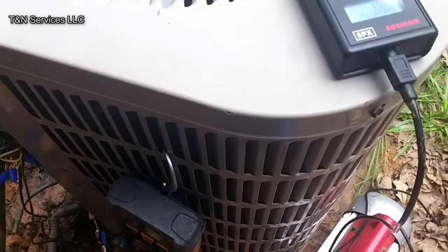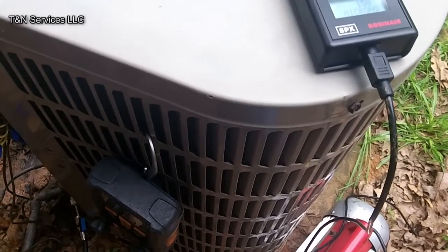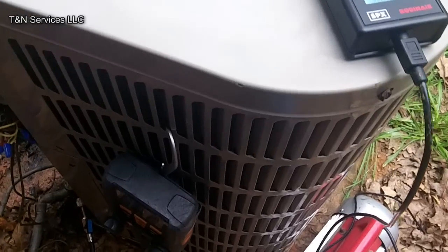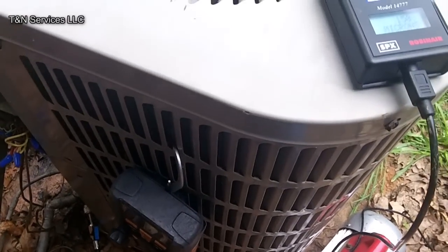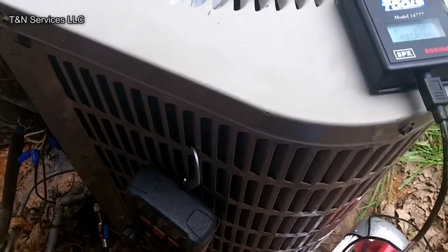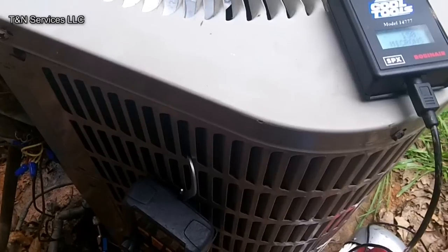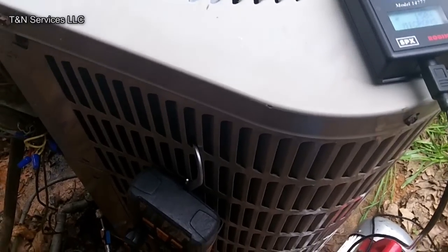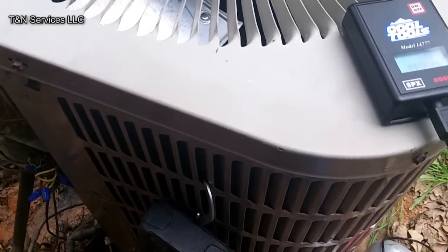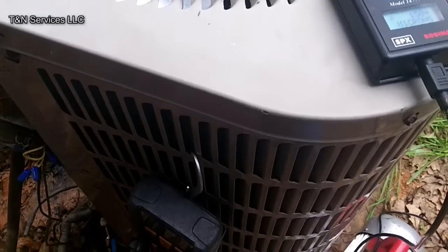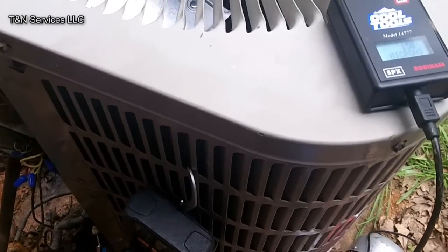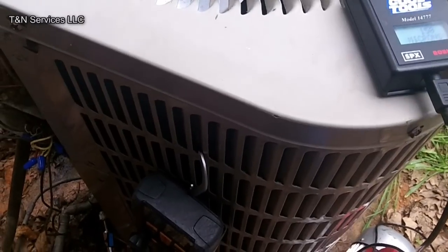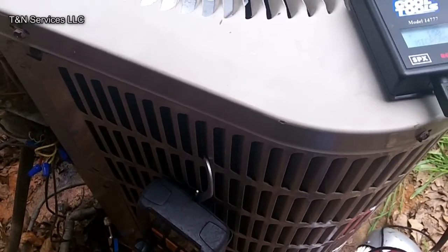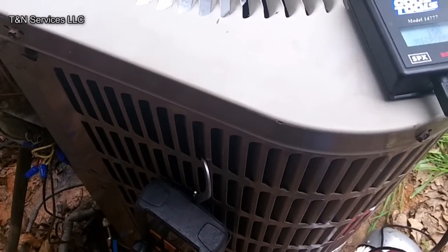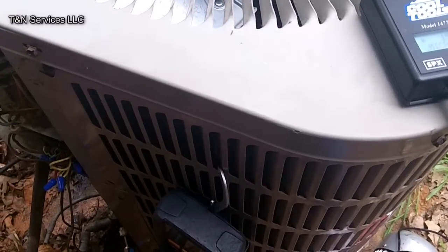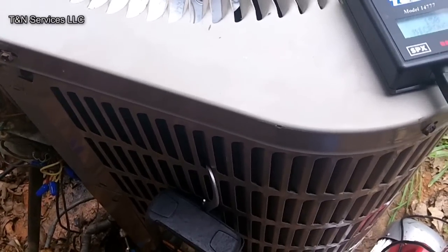And that's something else I want to touch on. If all you're doing is depending on what your superheat is, and let's say it's 75 in the house, and you have a 55-pound suction, but you have your target superheat at 21 degrees, there's actually a problem. So you've got to know what your pressures are supposed to be, and then what your superheat is supposed to be. If all you're doing is depending on superheat, it's not going to work very well.